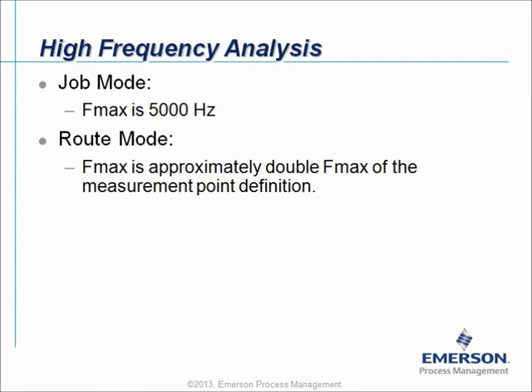The High Frequency Analysis module can be accessed from two different starting points. If you start this module in the job mode, there will be a spectrum measured with a default Fmax of 5000 Hz. However, if you start the same application from the Route Mode, there will be an additional spectrum measured and stored with approximately double the Fmax that was specified in the measurement point definition.